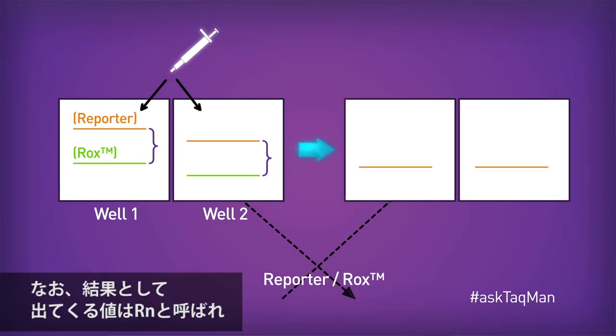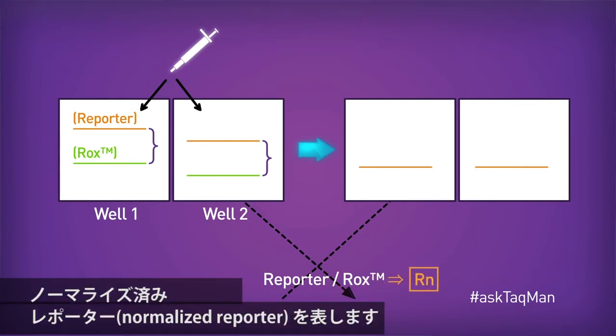The instrument will collect these paired measurements in every well at every cycle, and then divide every reporter measurement by its corresponding ROX measurement at the end of the run. As a result, the precision of our data goes way up. The value that results is called Rn, which stands for normalized reporter.